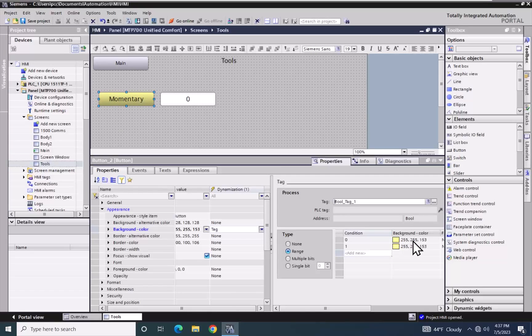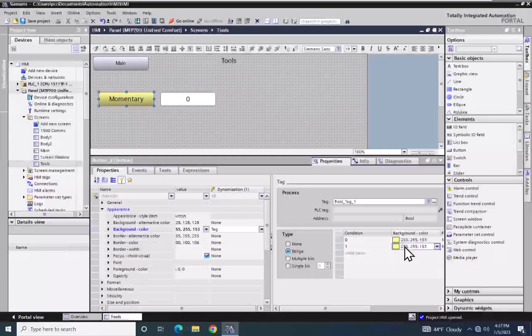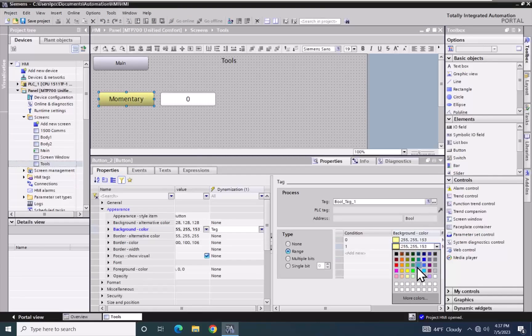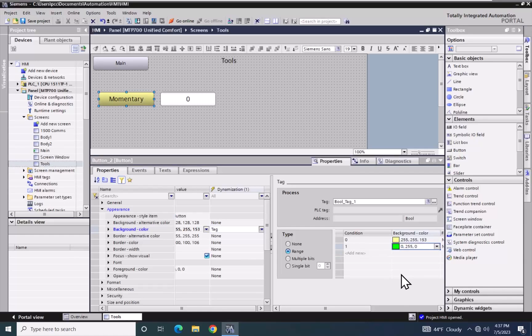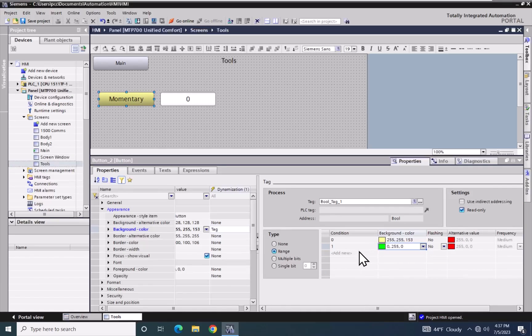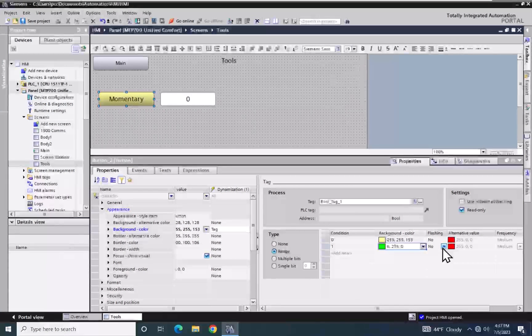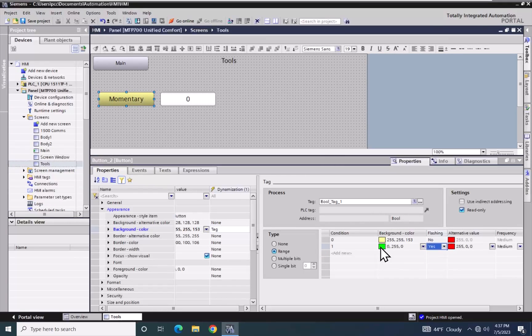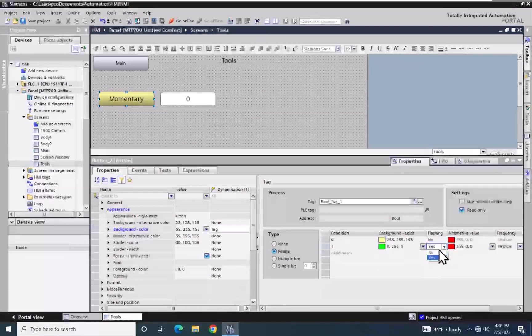So condition zero the background color will be yellow. For condition one I'm going to change that — I will click on the background color for condition one, select the drop down, and pick a green color. I can also enable flashing, and if I enable flashing then it will flash between the green and the alternate value which is going to be red. But I'm not going to do flashing here.